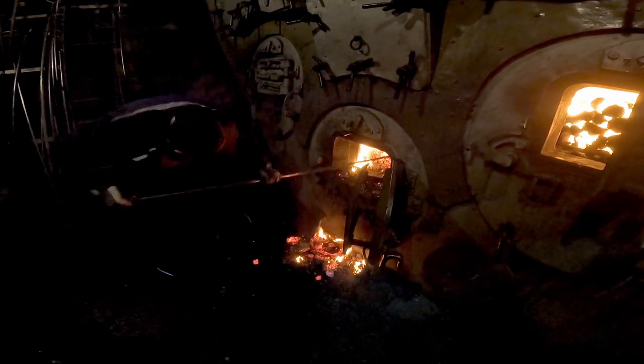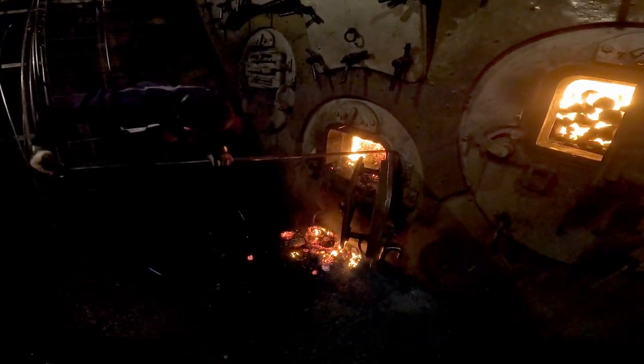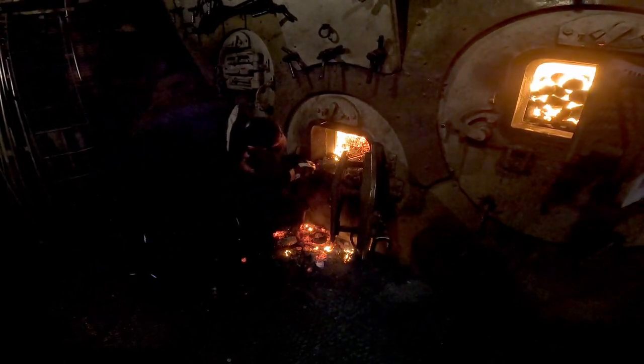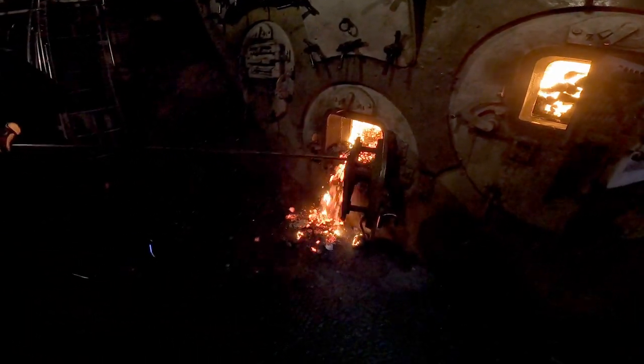And what is this? That is slag. This is almost the worst case when slag builds up. How come? The oven temperature was too high. The oven temperature is at about 800 degrees centigrade normally. The remains of the coal build regular ash. But if the temperature is above 1000 degrees Celsius, the remains melt — and that causes the slag. Exactly, that's the way the slag builds up.